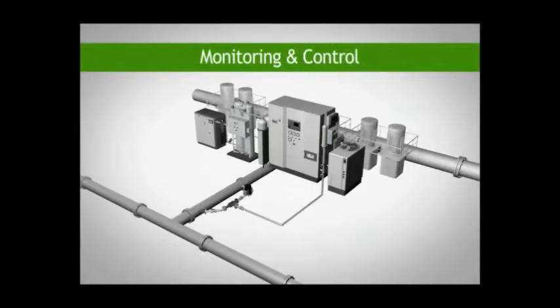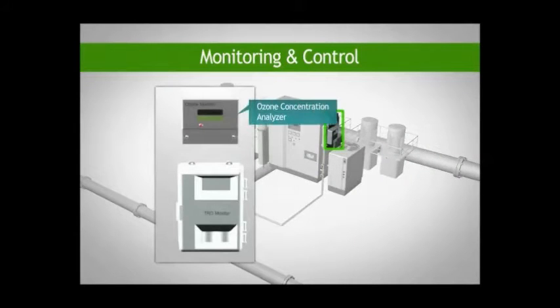The fourth component is the monitoring and control system, which includes an ozone concentration analyzer to control the ozone dosage used to treat the incoming ballast water, and a total residual oxidants or TRO analyzer to ensure that TRO are kept within safe levels.